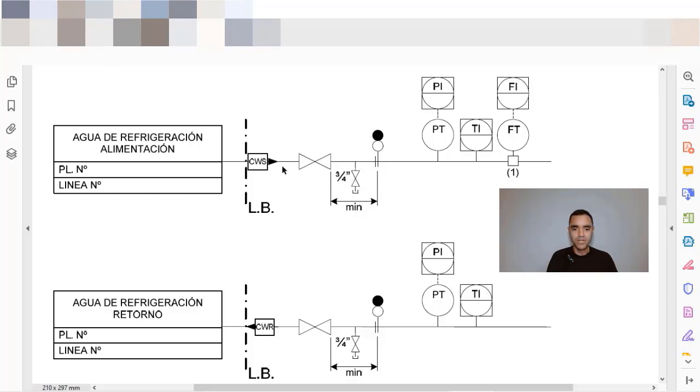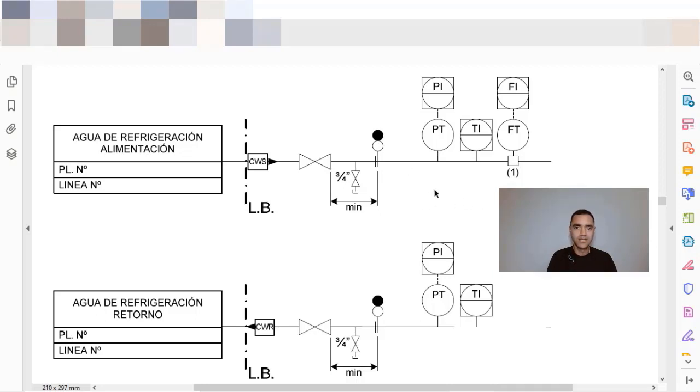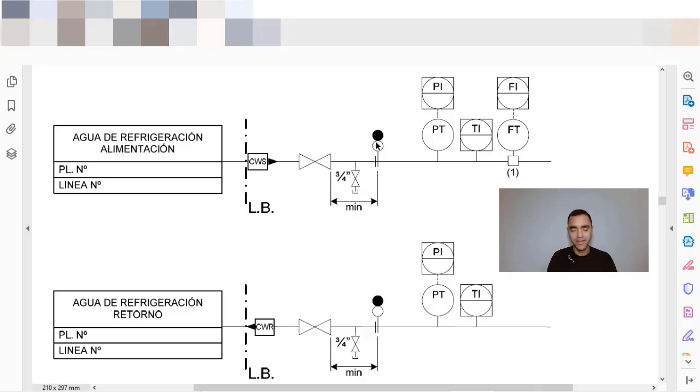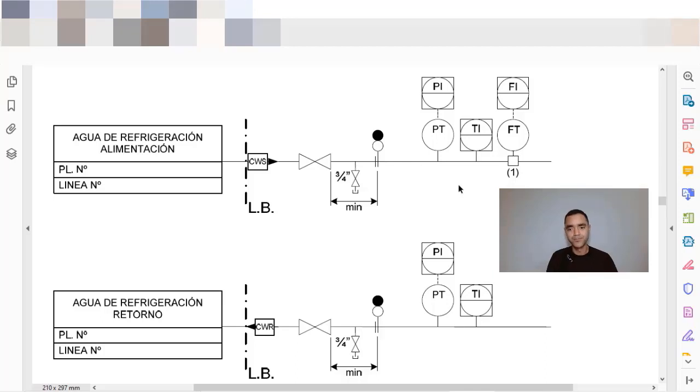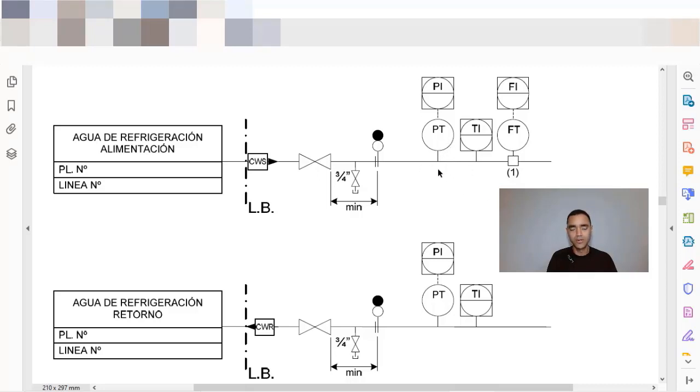We have isolation valve here. As it is water, there is no big concern, so there is no double blocking bleeds, no drain for oily system, and of course there is no vent to flare. So there is only one isolation valve, a drain valve, and a figure eight. As I told you, the white part represents that the figure eight is opened. As battery limits, to make sure that the supply complies with the requirements in the contract.